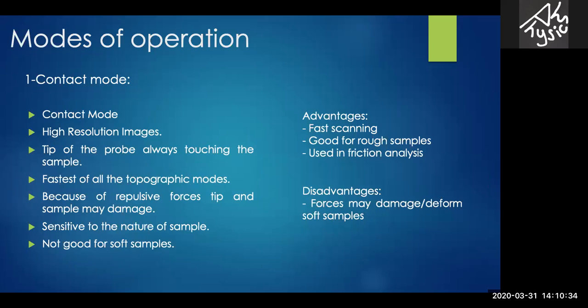Modes of operation. This microscope basically has three modes of operation: contact, non-contact, and tapping mode. The first one is contact mode. In contact mode, the resolution is high. The tip of the probe is always touching the sample. It is the fastest of all topographic modes.